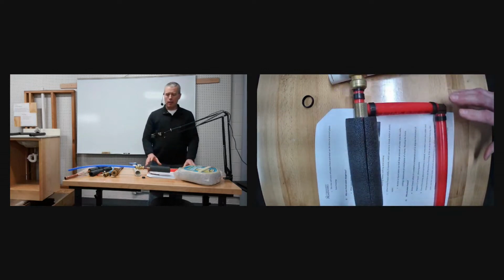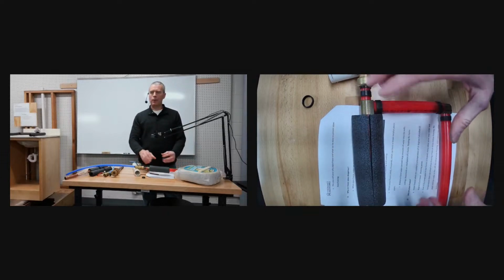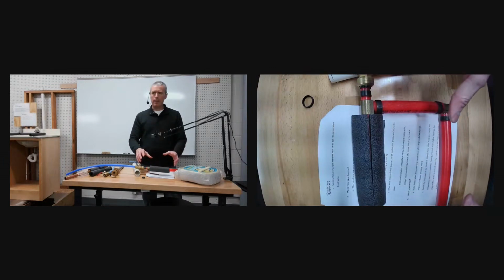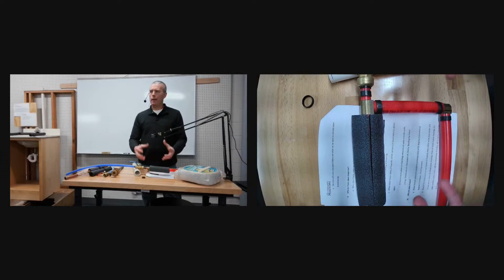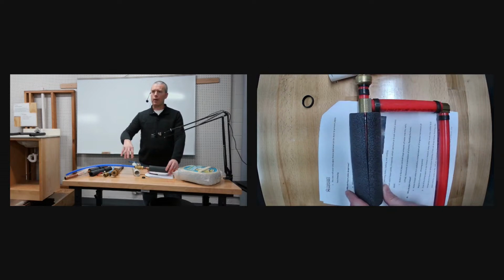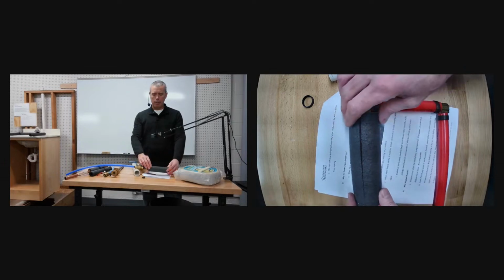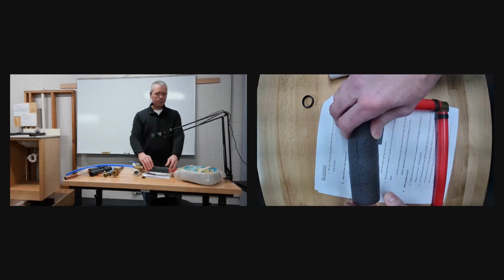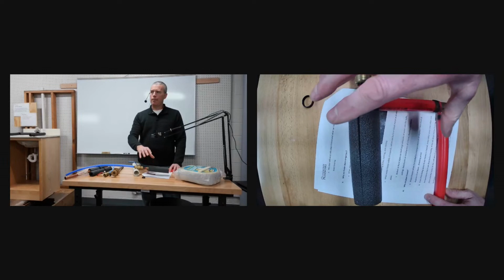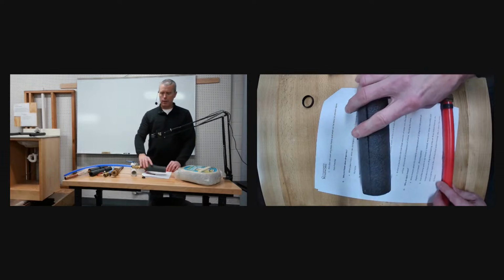The one thing that you have to make sure of, though, is that you're not trying to just insulate a pipe, even in the outside cold. There's got to be warmth around that insulation. You can't just run a cold water line, lay it on the ground, wrap some insulation around it, and expect it not to freeze. You're basically keeping this pipe insulated from the cold. So if it's in a spot that's not heated, it's still gonna freeze. The insulation is not gonna make a difference.